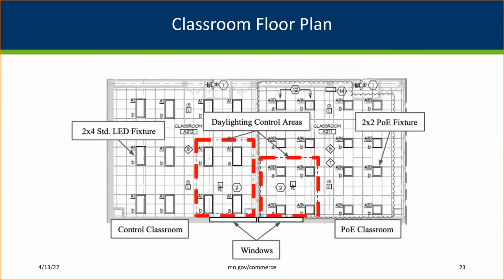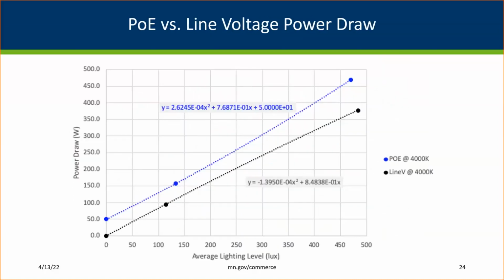Both have daylight coming through the existing south-facing window. The PoE classroom has 16 PoE 2x2 troffers, and the control room accommodated 12 AC-powered 2x4 troffers. Both systems have daylight control, occupancy sensor control, and both have a wall switch that can dim the lights. The two systems provide equivalent light output to the two classrooms. The AC-powered lights' energy use was monitored at the panel with CT and eGauge, and the PoE lighting fixture energy use was pulled from the network switch with an SNMP script. The lighting performance of the two systems is comparable.